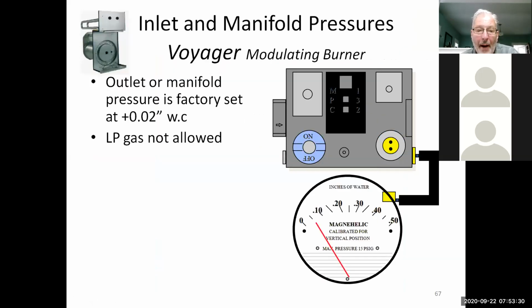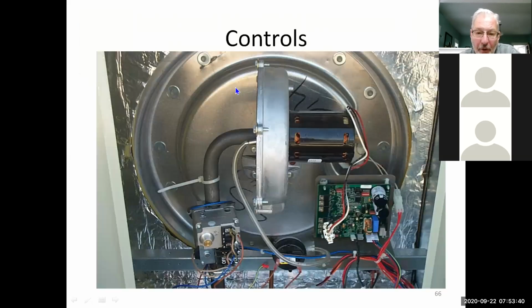They actually run positive. They run a 0.02 positive pressure, because of the pressure switch. One of the things on these units, if you look at it, the pressure switch is actually in line with the gas valve. So if that pressure switch doesn't close, it could throw a gas valve error. That's also tied in with the limit, so it could throw a limit error too.